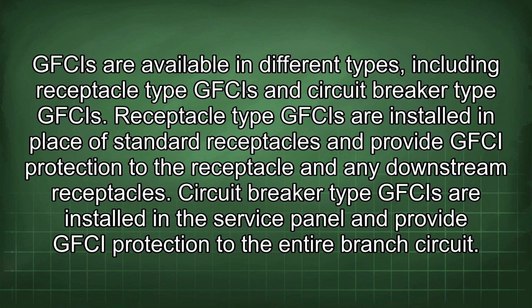GFCIs are available in different types, including receptacle-type GFCIs and circuit breaker-type GFCIs. Receptacle-type GFCIs are installed in place of standard receptacles and provide GFCI protection to the receptacle and any downstream receptacles. Circuit breaker-type GFCIs are installed in the service panel and provide GFCI protection to the entire branch circuit.